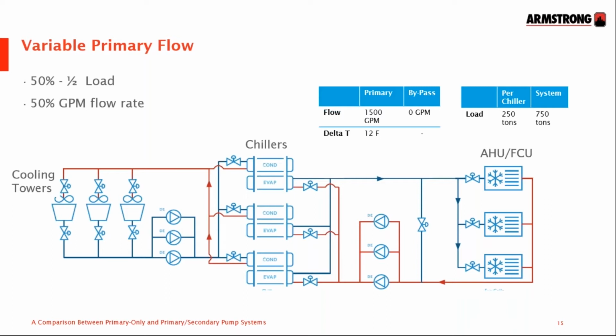Chiller plant optimization is provided by Armstrong's Optivisor system on a retrofit basis, and our IPC 11550 for new build projects. For this example, we've opted for energy-based sequencing as opposed to load-based sequencing, as these are variable speed chillers, which will now be running more efficiently at half load. So we have the pumps slowed to 75% of flow through the three chillers, each 50% loaded, cooling water from 56 down to 44, and running at 50% loaded, their efficiencies improved compared to what they were at full load.